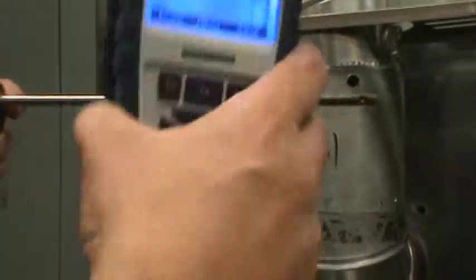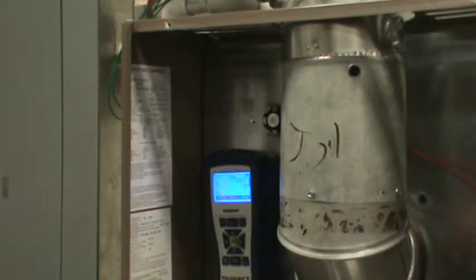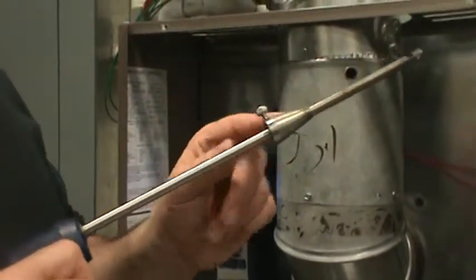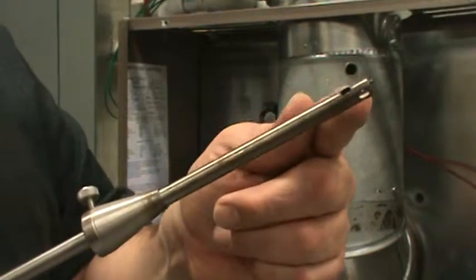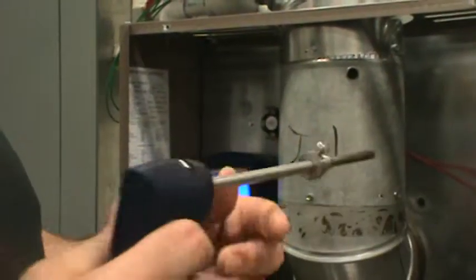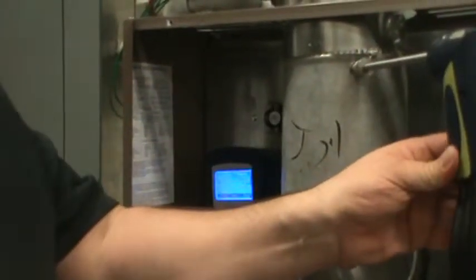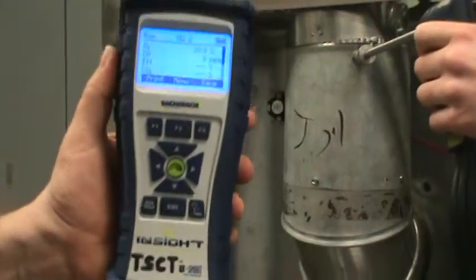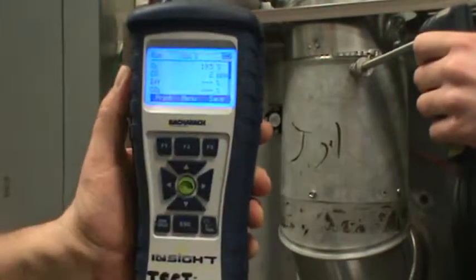Here's the other end. It's open here. This thing has a pump in it. We're going to stick it over here for now. We'll come back to it and get some readings. I'm going to take my probe. It has a piece on here so you don't go too far. I'm going to try to keep this out of the smoke and soot. If there's any soot or debris on the smoke pipe, you don't want to go the whole way to the other side. We're going to insert this into my smoke pipe. And we're going to then look at our numbers then. So right now, we have it inserted into the smoke pipe. We're running. And we're waiting for my oxygen starting to drop.